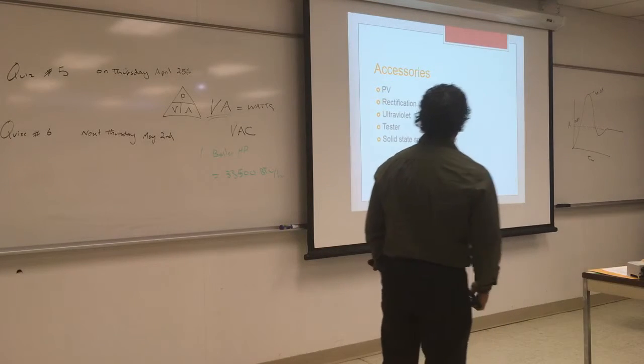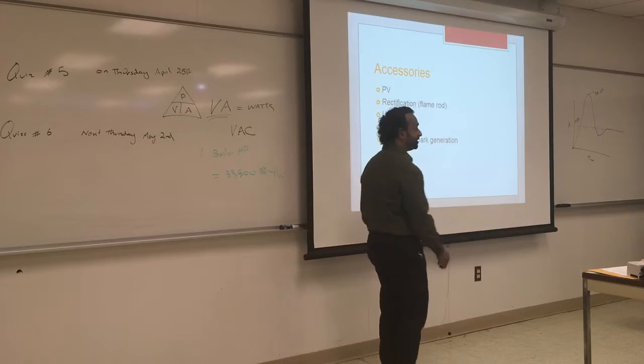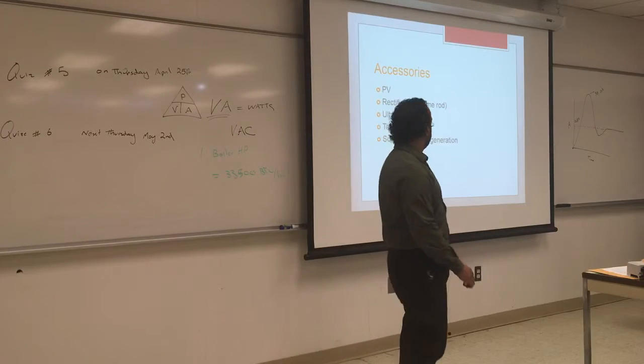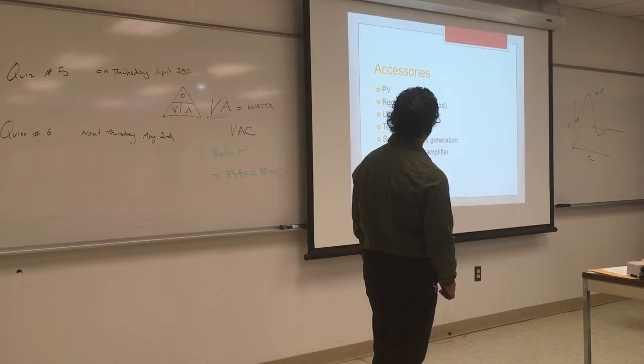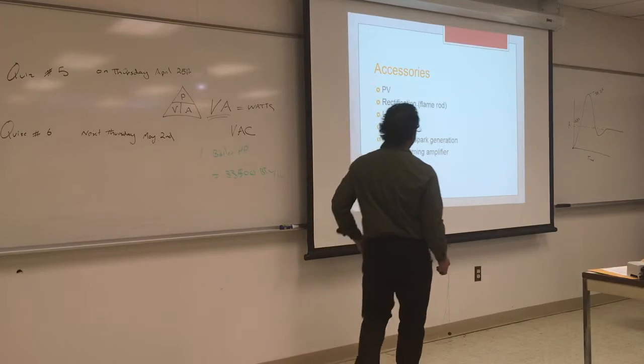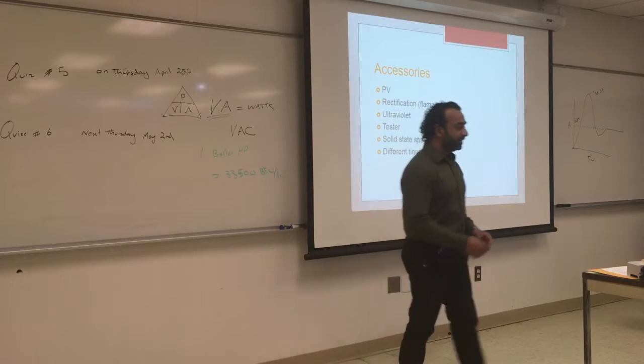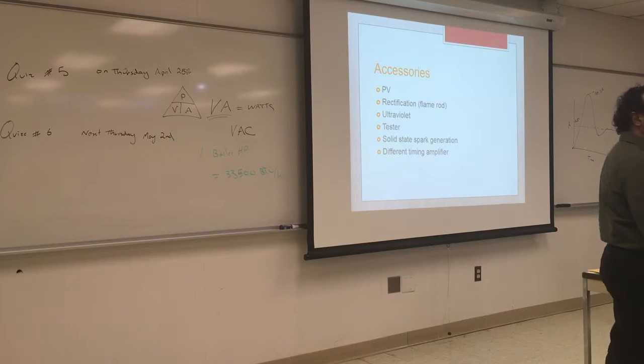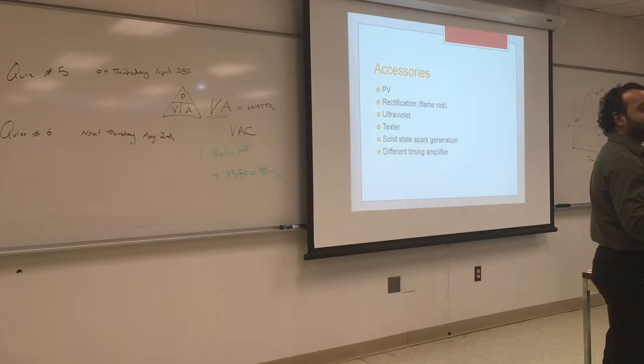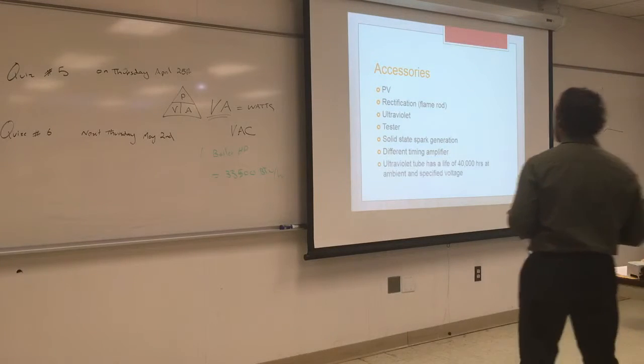Solid state spark generation. There's also another option you can put into the control: different timing amplifiers. What is a timing amplifier? Again, it's included in the cartridge here. It's how much time we have, for example, from 1 second to 2 seconds to 3 seconds. You can change that by changing the amplifier.